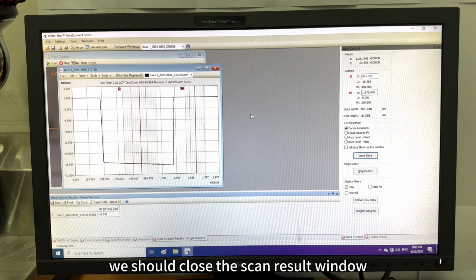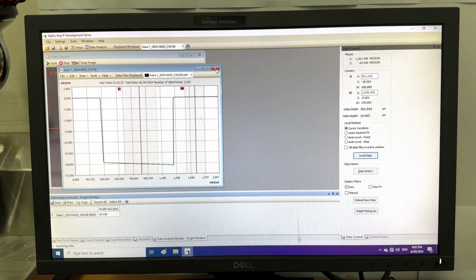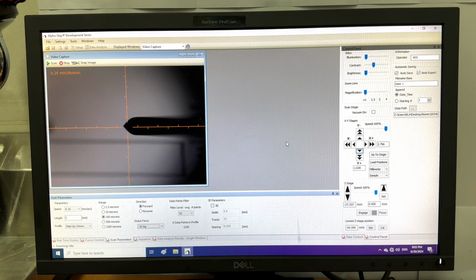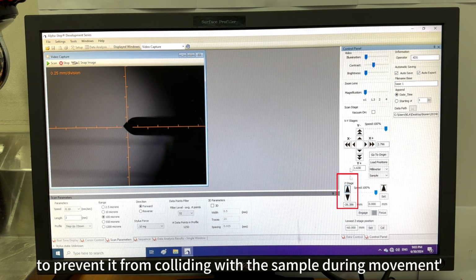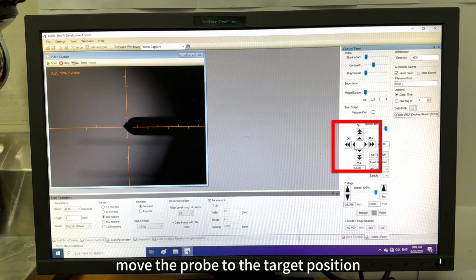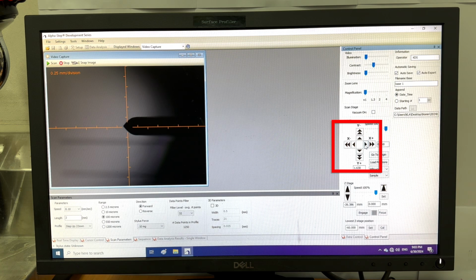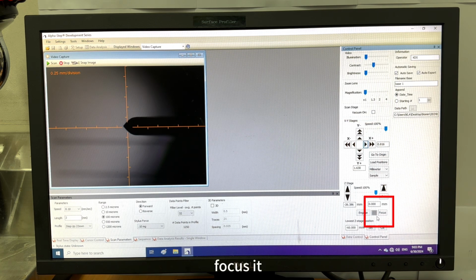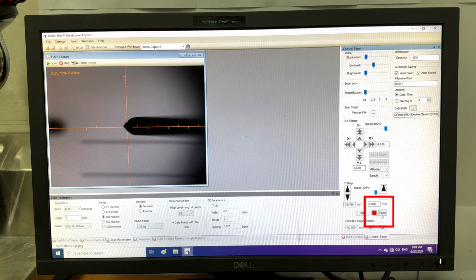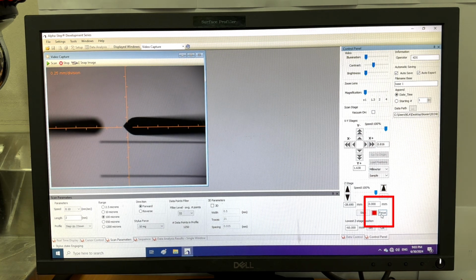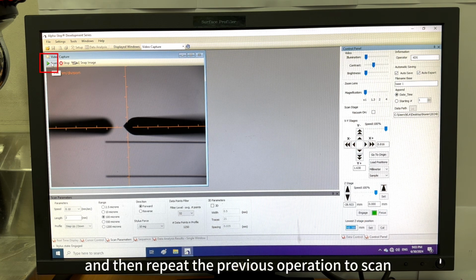After use, we should close the scan result window. If we need to scan another point, we need to lift the probe again to prevent it from colliding with the sample during movement. Move the probe to the target position. Focus it. And then repeat the previous operation to scan.